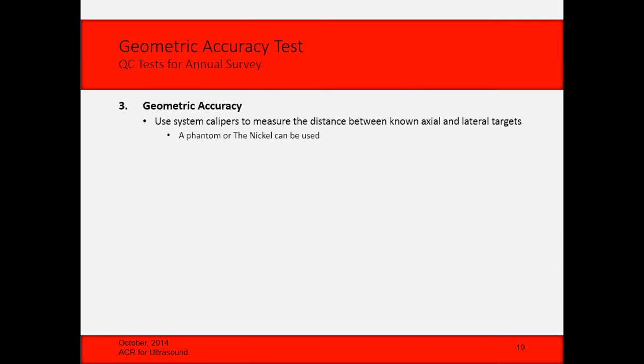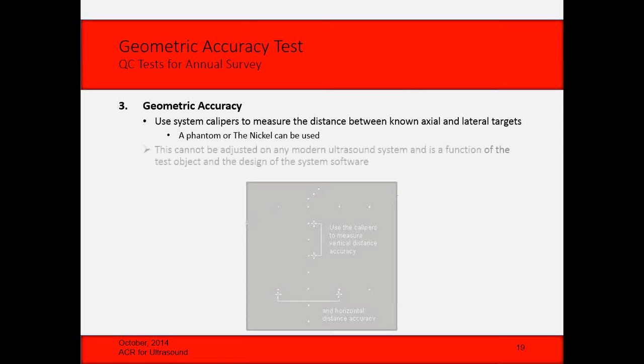Then geometric accuracy, this is where the calipers are measuring the distances correctly. You can use a phantom or the nickel for that. But as we know, this can't be adjusted on modern ultrasound systems. They're all digital clocks and everything. So there have been mistakes made on this, by the way, because the software engineers have to do geometric correction on mechanical and curved array and sector array probes. So if they get that calculation wrong, you can actually get the wrong caliper measurements. So what I always tell people these days is you want to measure it when you get a new system or anytime the software is updated. If they change the software version on your system, you should really check the geometric accuracy on the probes.